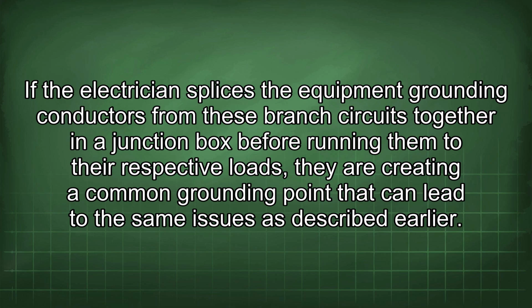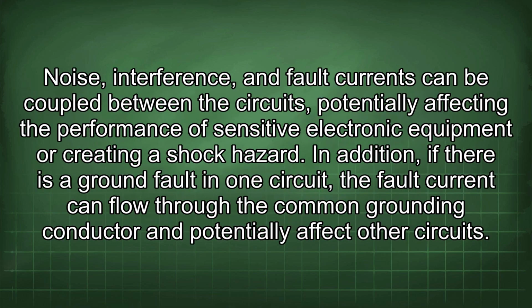If the electrician splices the equipment grounding conductors from these branch circuits together in a junction box before running them to their respective loads, they are creating a common grounding point that can lead to the same issues as described earlier. Noise, interference, and fault currents can be coupled between the circuits, potentially affecting the performance of sensitive electronic equipment or creating a shock hazard. In addition, if there is a ground fault in one circuit, the fault current can flow through the common grounding conductor and potentially affect other circuits.